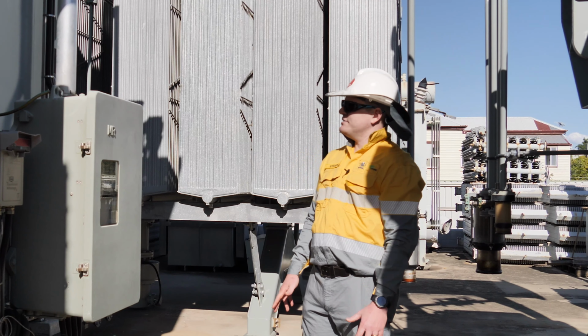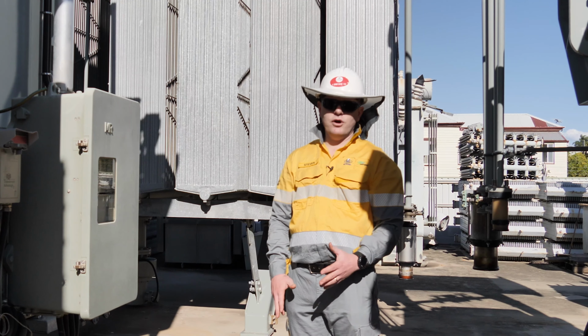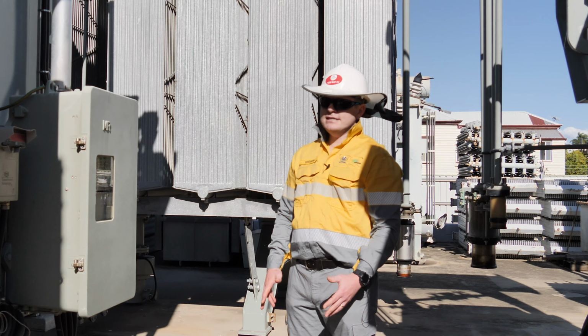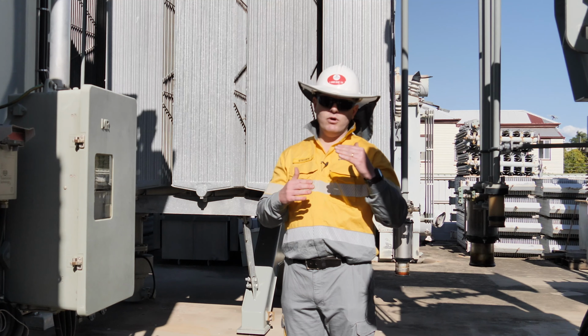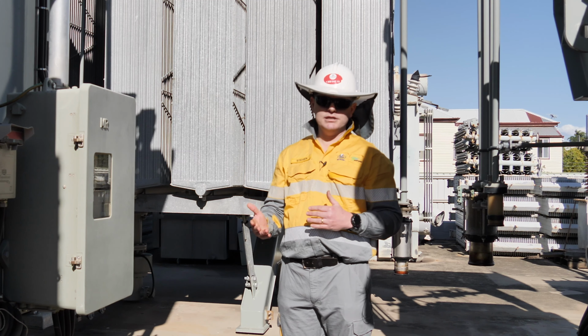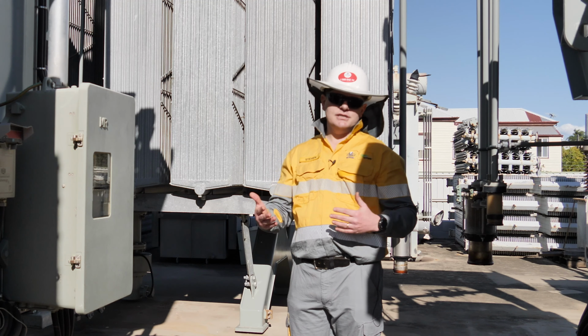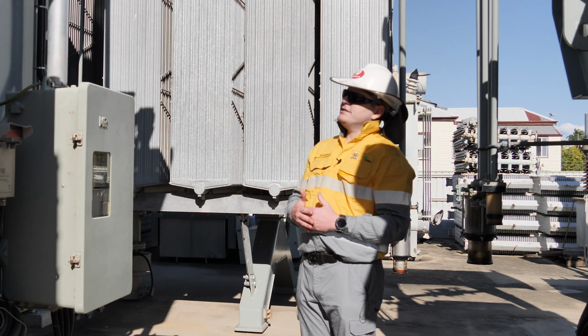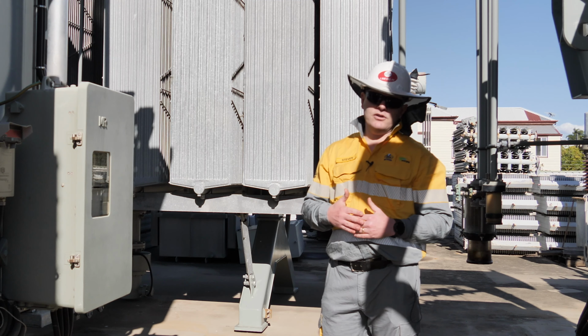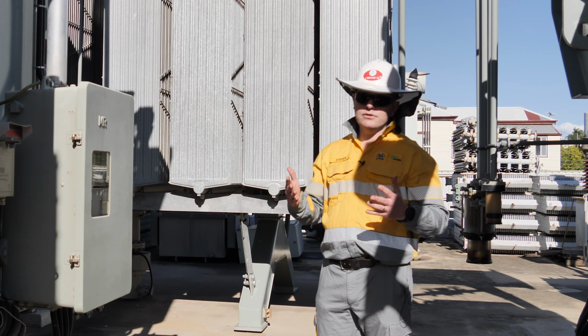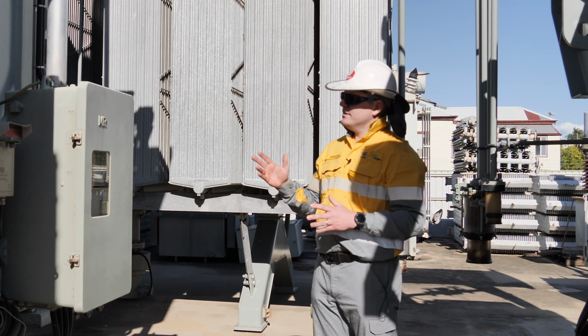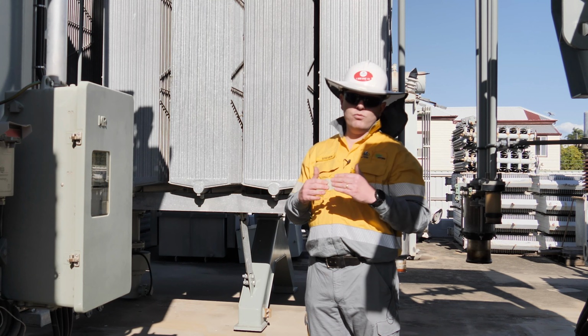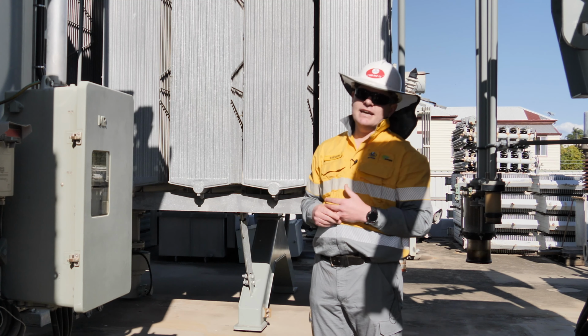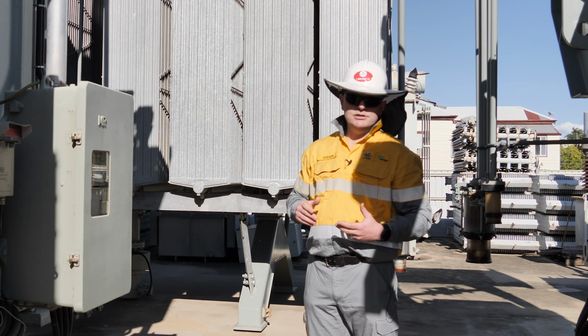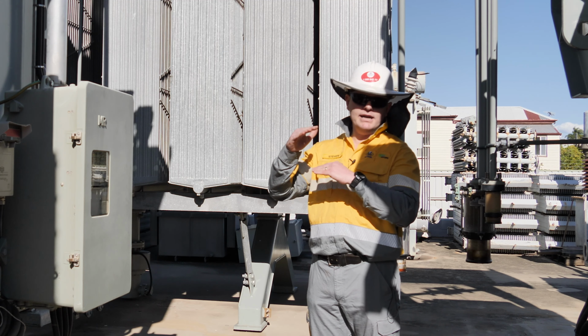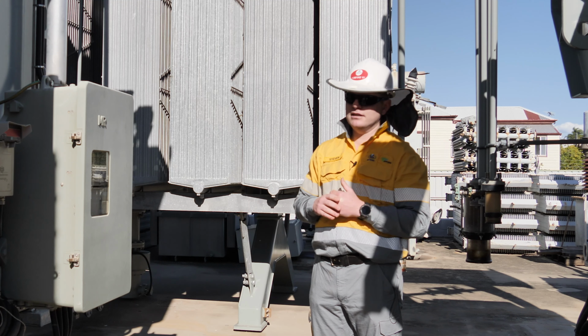Another really important part of this transformer is the on-load tap changer, or OLTC. What the OLTC does is it can change the winding ratio between the primary and secondary windings of the transformer in response to changes in system voltage. So if we say, for instance, that the voltage on the 132 kV side of this transformer dips to, say, 131 kV, which can happen sometimes, the tap changer can then operate to change the winding ratio in the main tank to make sure that the secondary voltage stays within an acceptable range within that 66 kV secondary voltage.